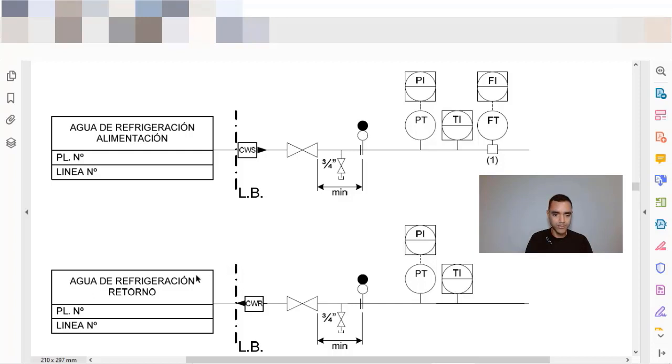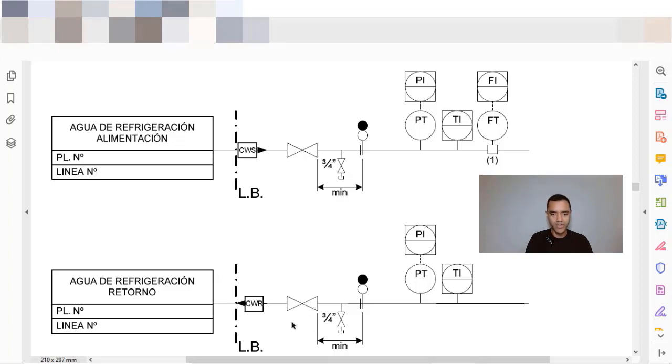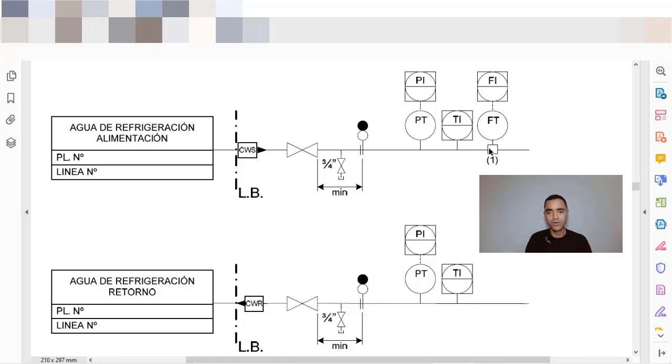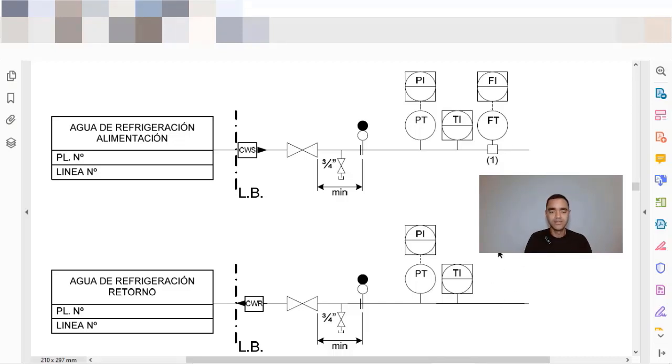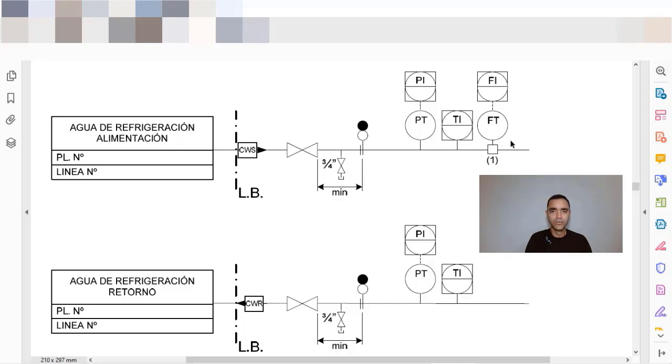The cooling water return, we have the same arrangement or very similar arrangement with the dash point line to represent the battery limit, the identification of the fluids. Now it's return. We have the isolation valve, drain valve, and now we have only the temperature and pressure and we don't have the flow measurement. And why we don't have the flow measurement? Because a cooling water system is a closed loop system, so it's not expected that you lose flow during this process.